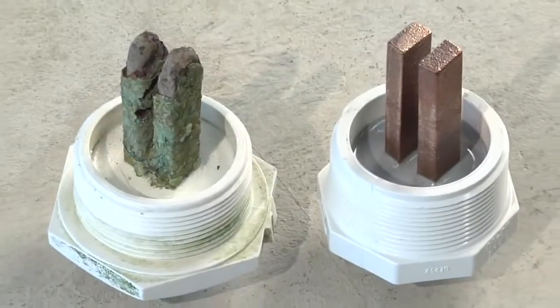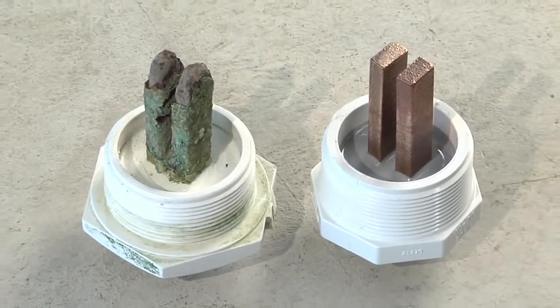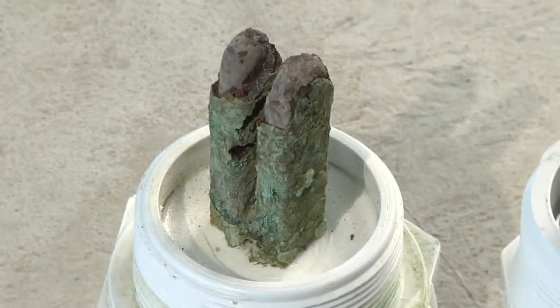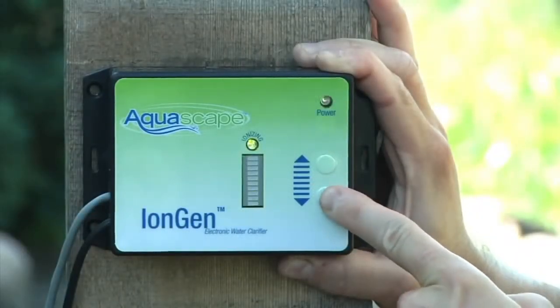And today, I'm going to provide you some technical tips on how to maximize the performance of the IonGen water treatment system. One of the most important factors to having success with the IonGen is to ensure there's good water circulation across the probe. An excessive buildup of scale in the bars is an indicator that there may not be sufficient water flow. The scale will decrease the distribution of ions being released in the water, as well as affect the ability to raise and lower the control panel's ionization level.